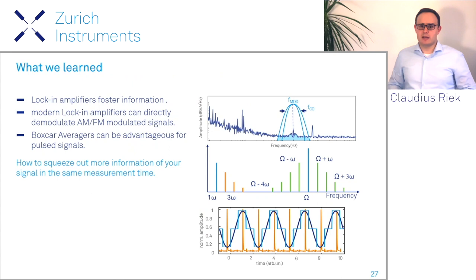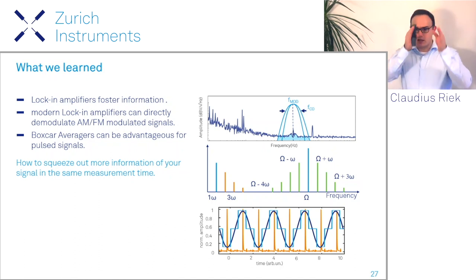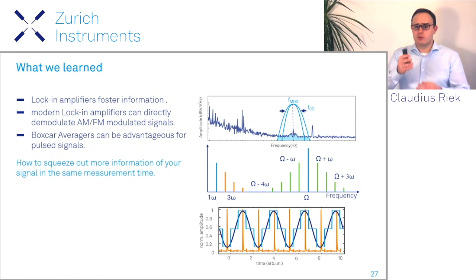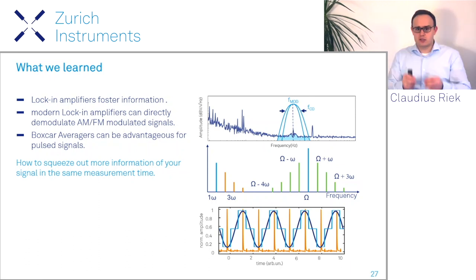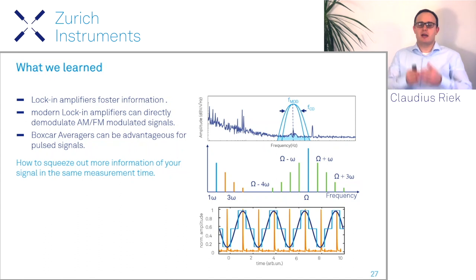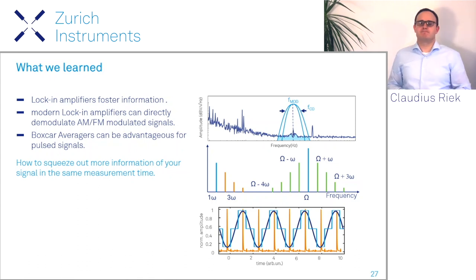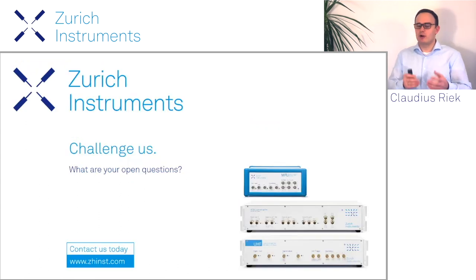To summarize: lock-in amplifiers extract information by acting as a bandpass filter, suppressing unwanted noise. Modern lock-in amplifiers can directly demodulate AM-FM modulated signals and recover side band signals without the need for tandem demodulation. Boxcar averagers are advantageous for pulsed signals, capturing more signal at higher harmonics of the fundamental modulation frequency. I hope I have shown you how to squeeze more information out of your signal in the same measurement time. Thanks for joining — if you have more questions, get in touch and let's discuss.